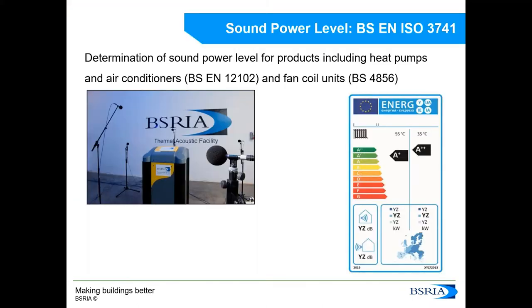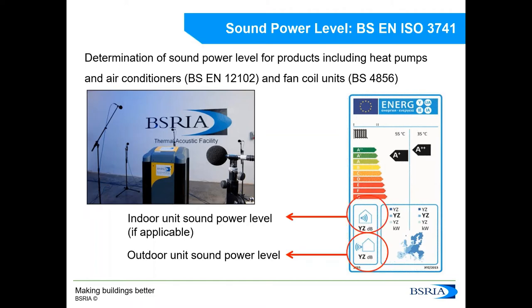Looking at common test methodologies: for sound power levels, there is a standard called BS EN ISO 3741, which covers measurement in a reverberation chamber. There are also specific test standards for particular product types such as heat pumps, air conditioners, or fan coil units. Many will be familiar with energy labels on domestic appliances such as fridges and washing machines — the same applies for heat pumps and air conditioners, and those energy labels include a determined sound power level to help manufacturers, installers, and suppliers compare products.